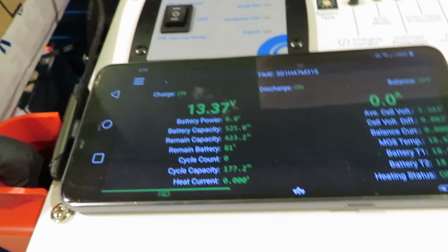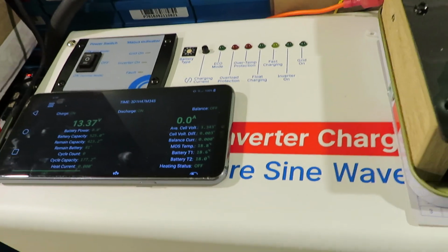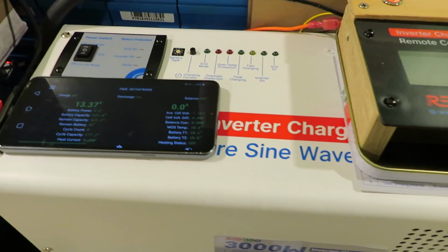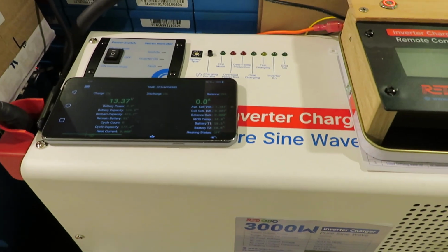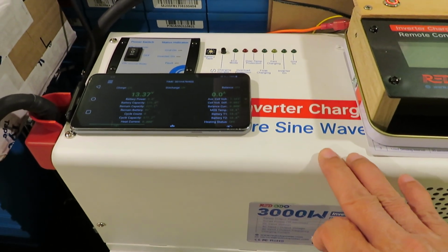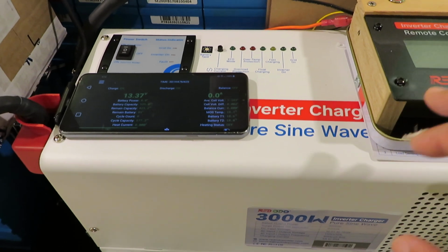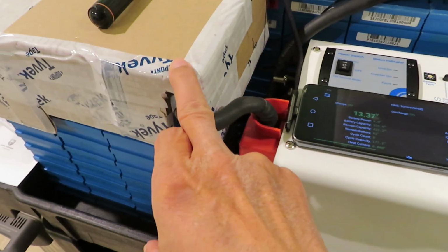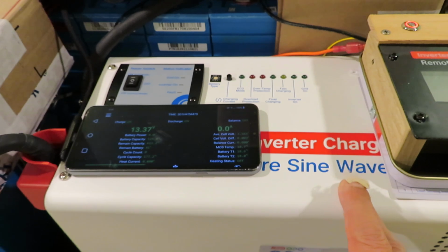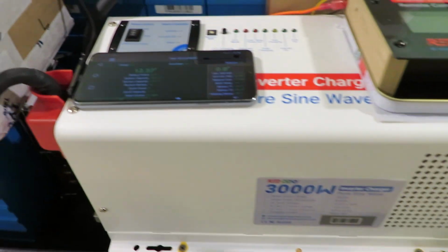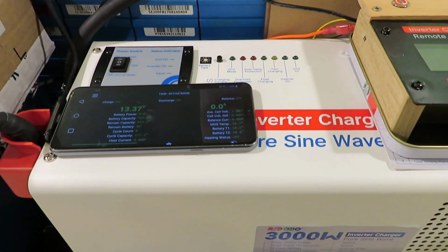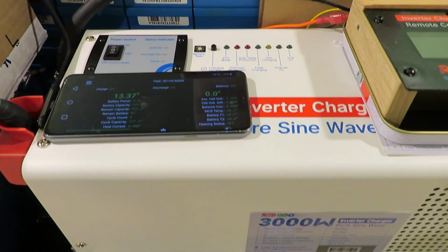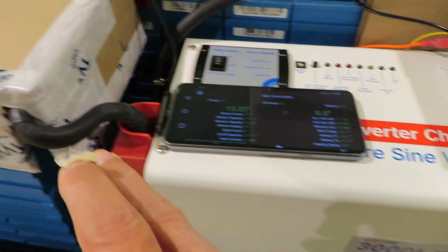So the next step is to turn on the inverter. It has to go through a sequence to make sure everything is working properly. The sequence is: battery comes on first, then the inverter comes on second, and then shore power last. When I shut it down, I reverse the sequence, undoing the shore power and turning off the inverter before turning off the battery.